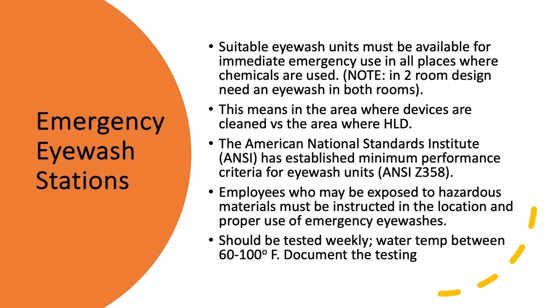There is a standard. ANSI has the minimum performance criteria for eye wash units. It's ANSI Z358. And it says that employees who may be exposed to hazardous materials must be instructed in the location and use of emergency eye washes. Eye wash should be tested weekly, and it has to include the water temperature, which needs to be between 60 to 100 degrees Fahrenheit. That's to prevent damage to eye tissue, and you should document all the testing.